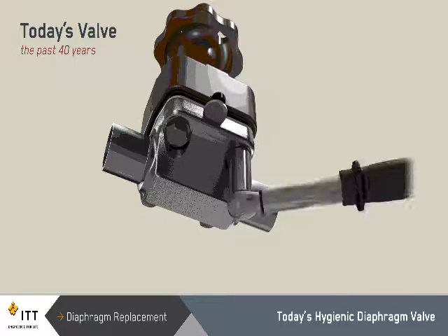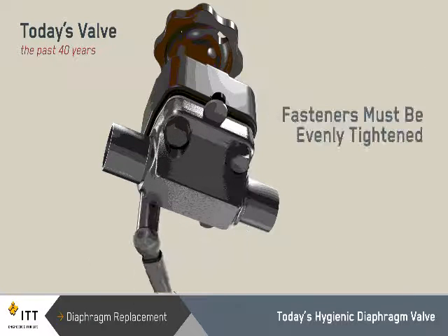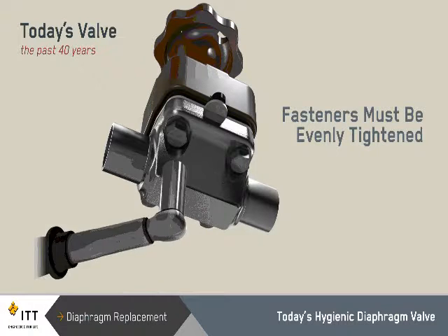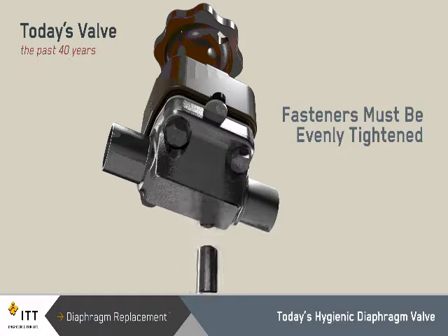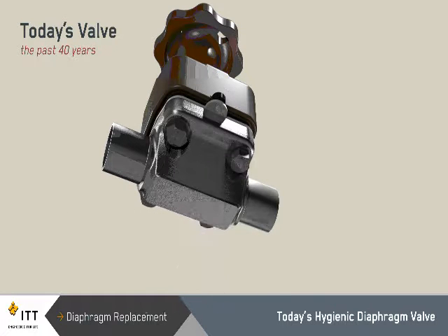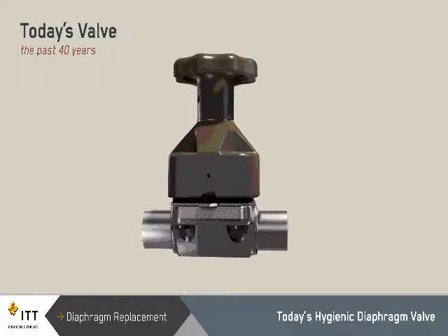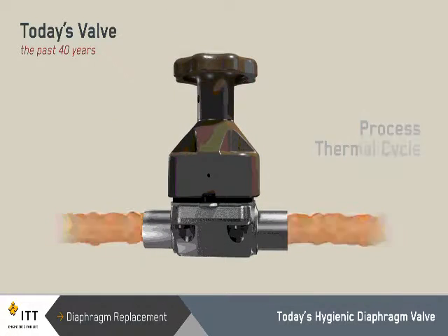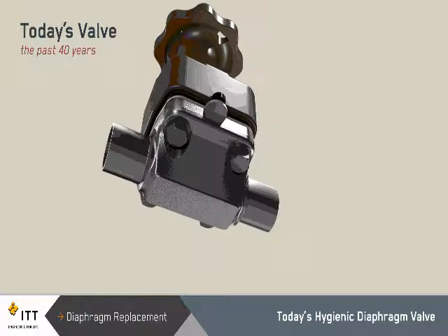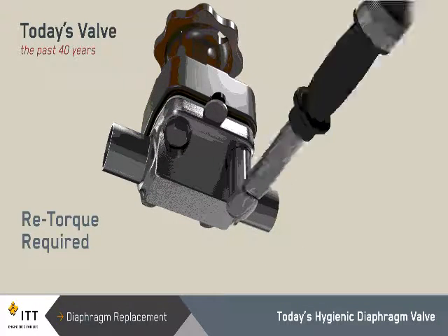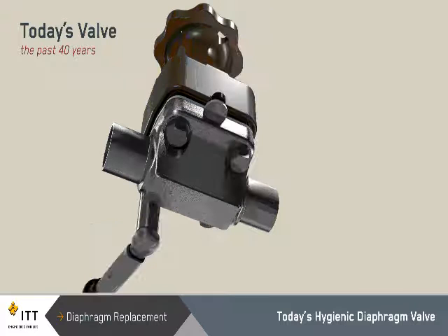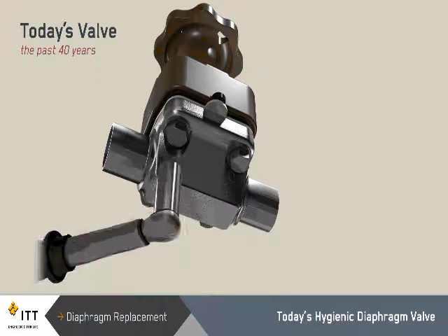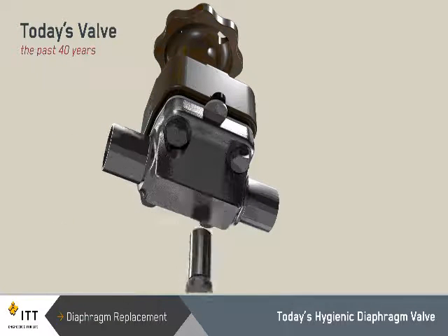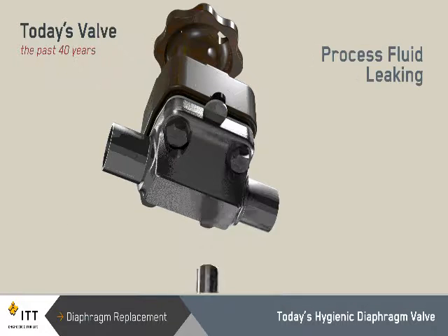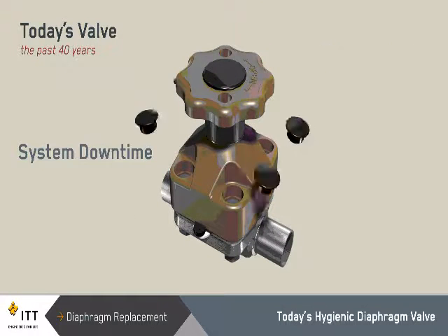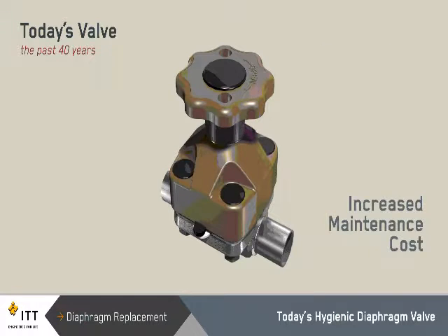After changing the diaphragm, the fasteners must be evenly tightened to the manufacturer's specifications to ensure a proper seal. These fasteners commonly require a retorque after the system has reached full operating pressure and temperature. Diaphragm replacement is a critical procedure, and improper installation can result in process fluid leaking, system downtime, and increased maintenance costs.